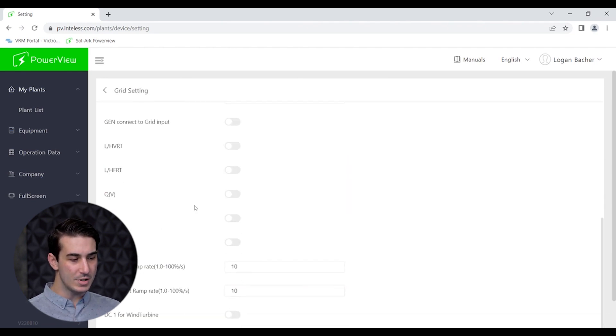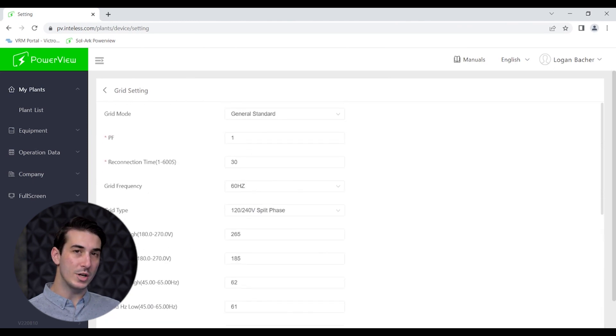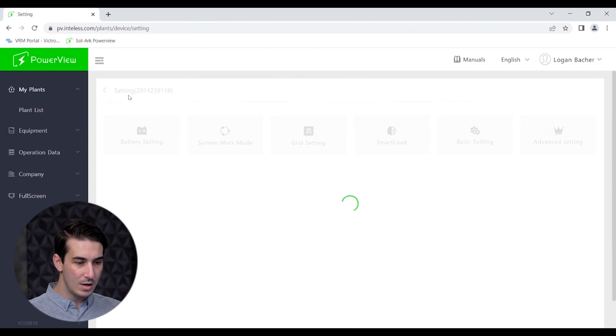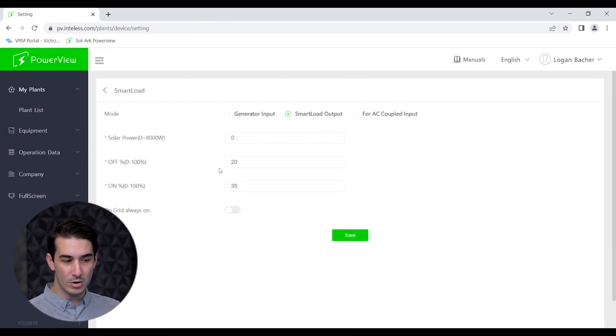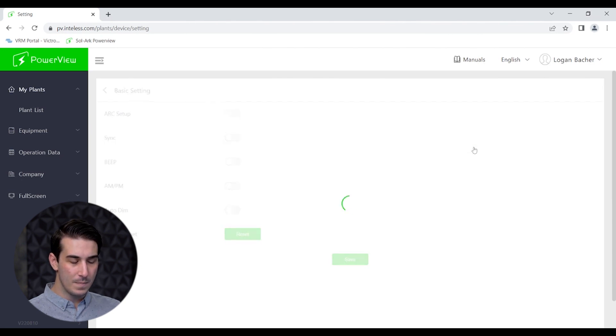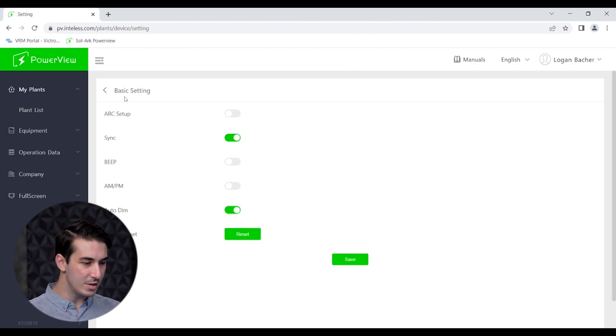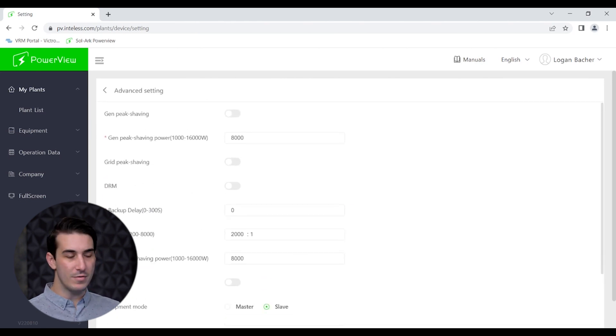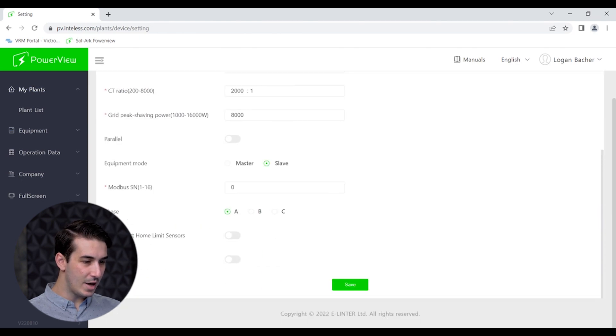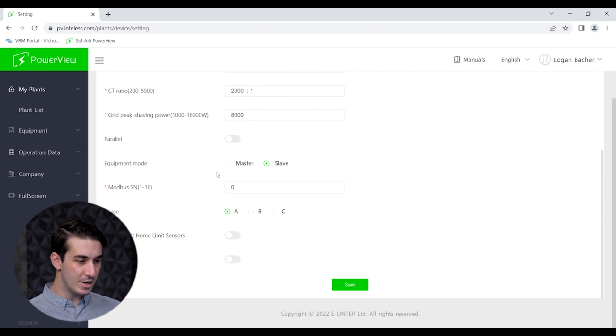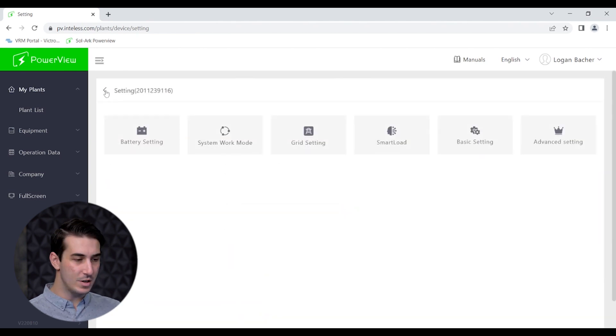Going back to settings you can look at the grid settings. This is mostly relevant I would say for systems that are going to be exporting to the grid. You can go in here and change things to match with what your utility might recommend for interconnection. There's a whole tab for the smart load setting on the solar converter you can configure. We've got some basic settings here. These all have to do with user preference stuff, how the alarms work, screen brightness, timeout settings, and things like that. And then the last group of settings you can view on PowerView is the advanced settings. Here you have things like peak shaving. If you have a multiple inverter system you can configure the master-slave relationship on this page.